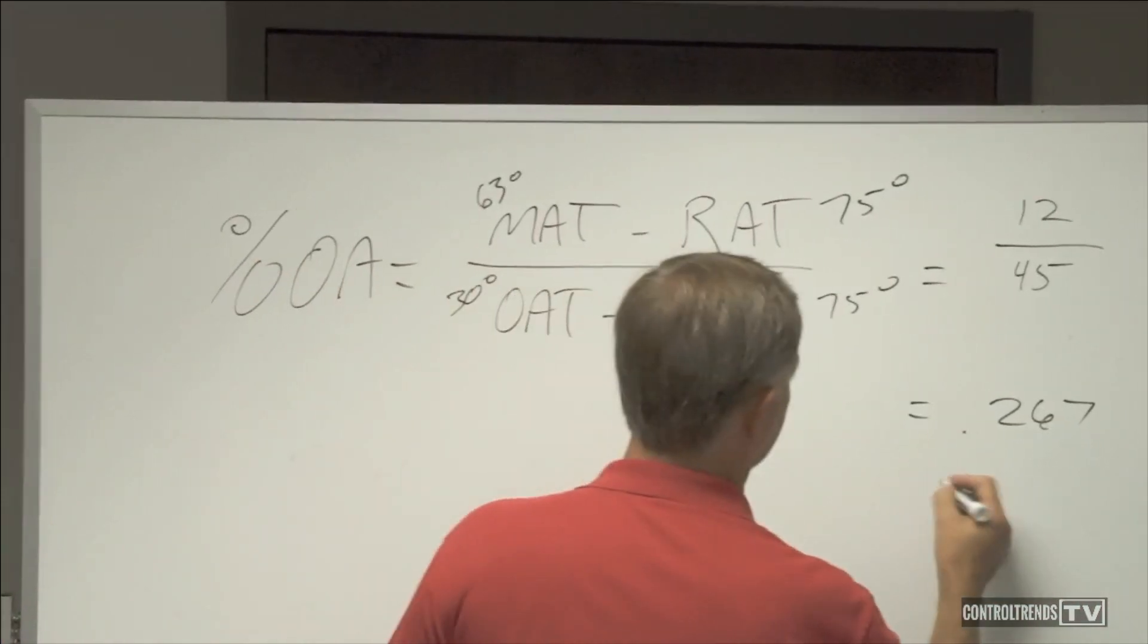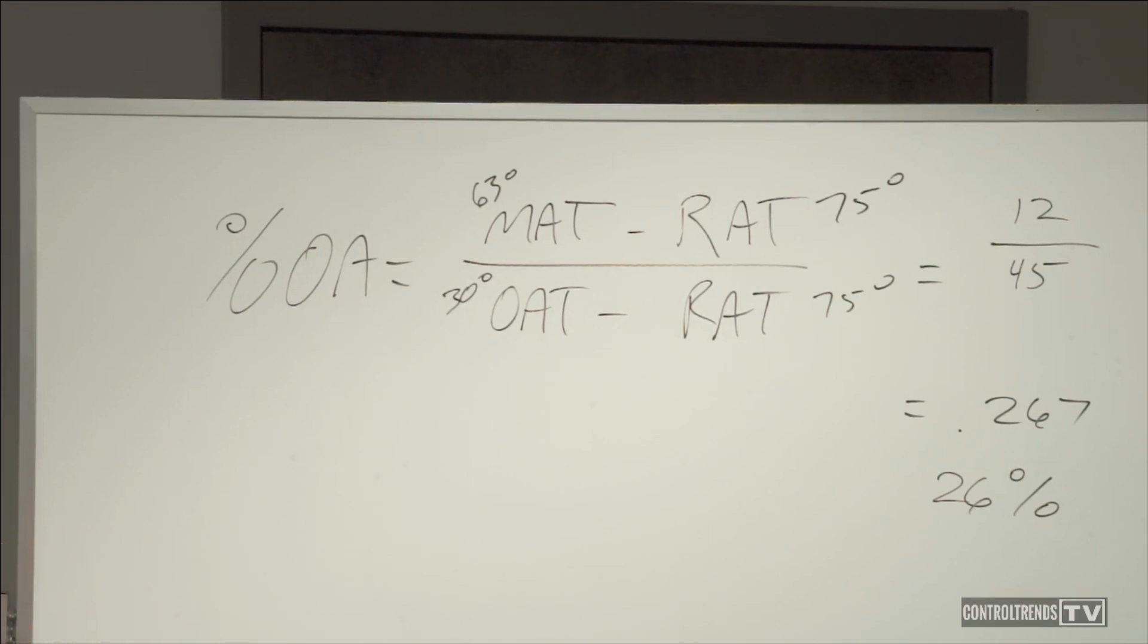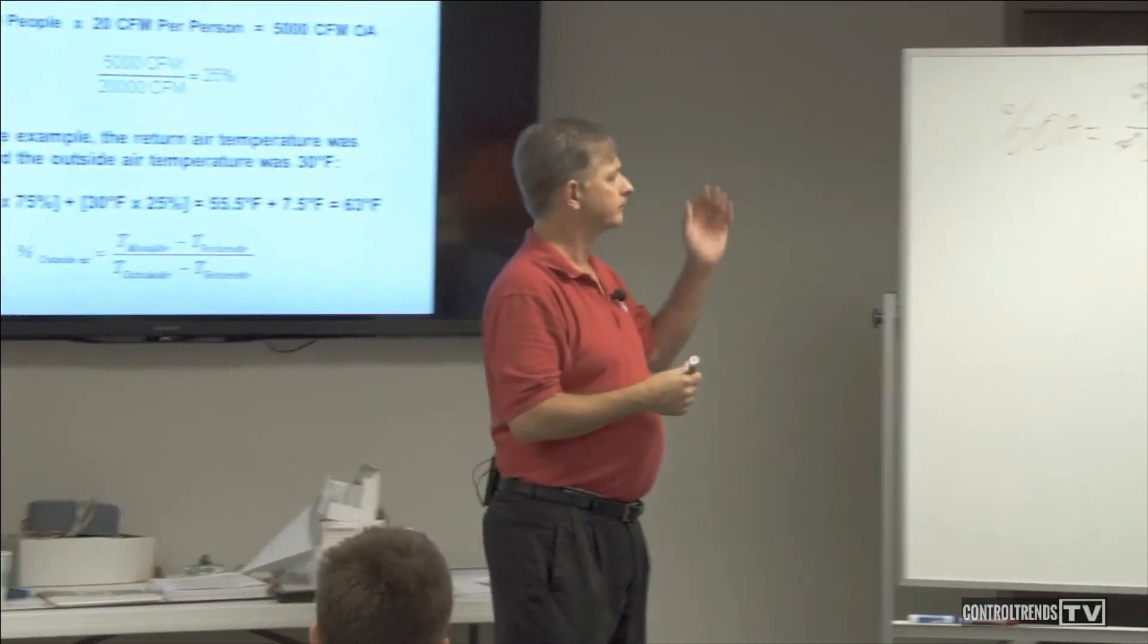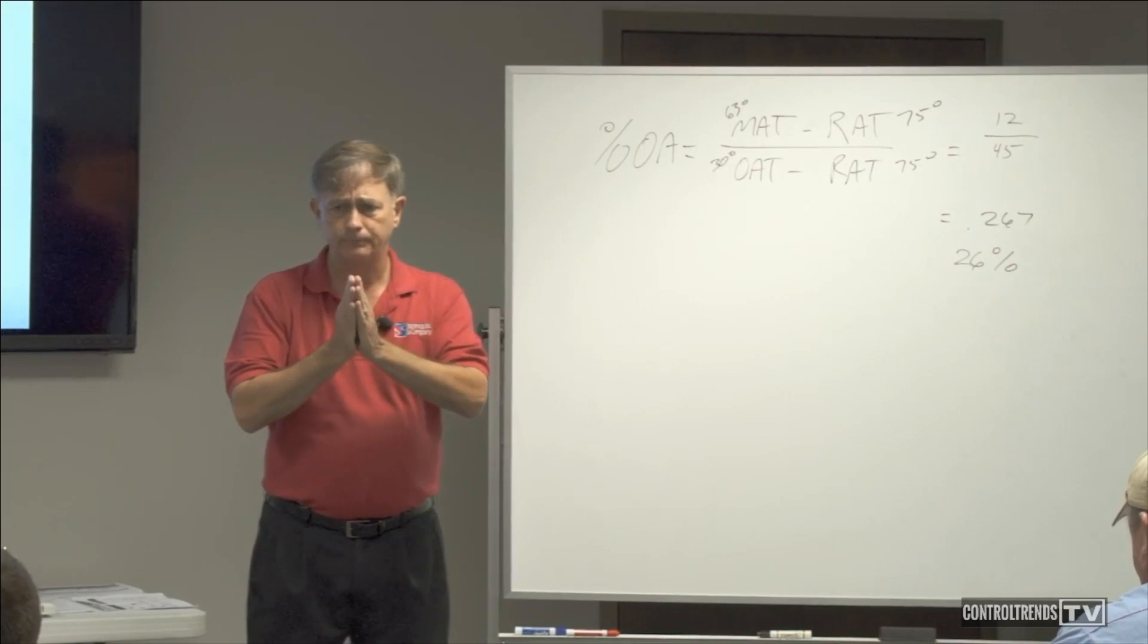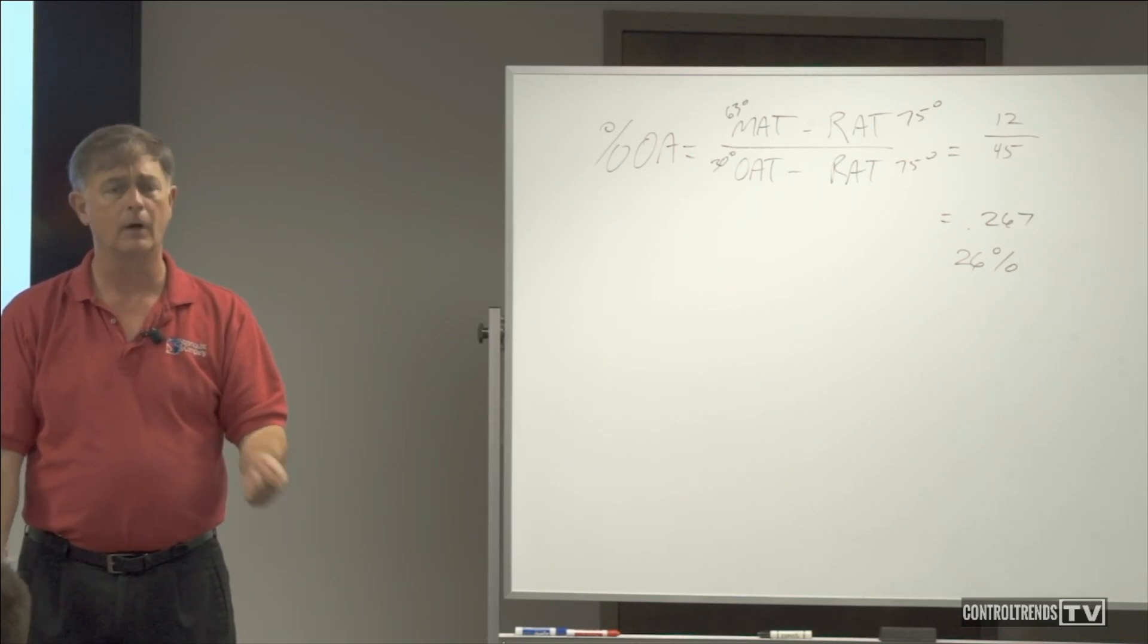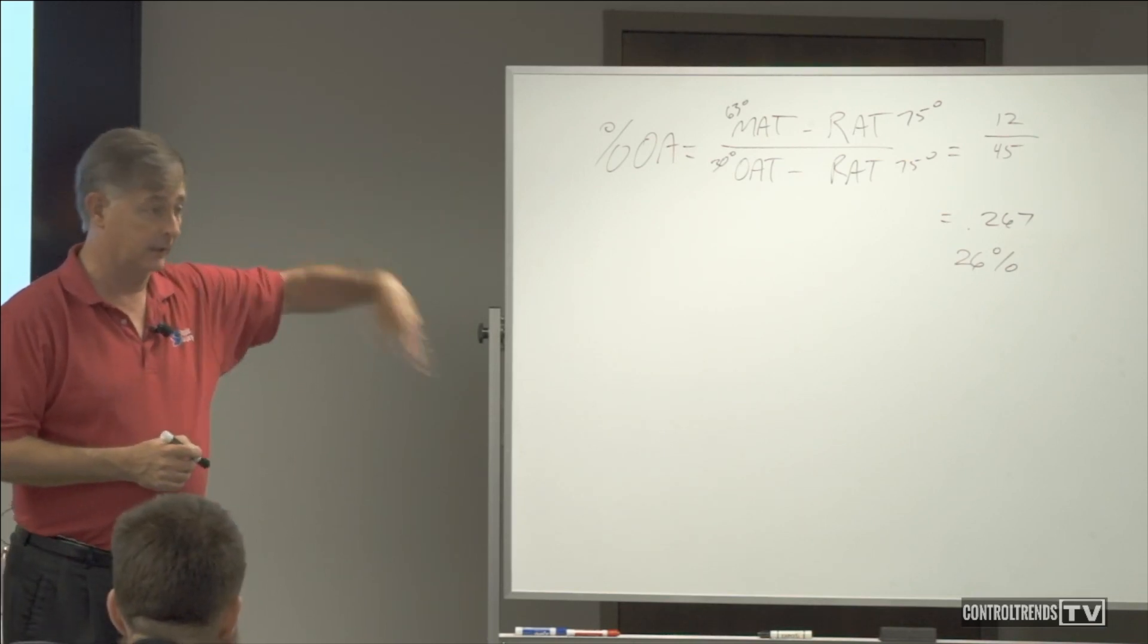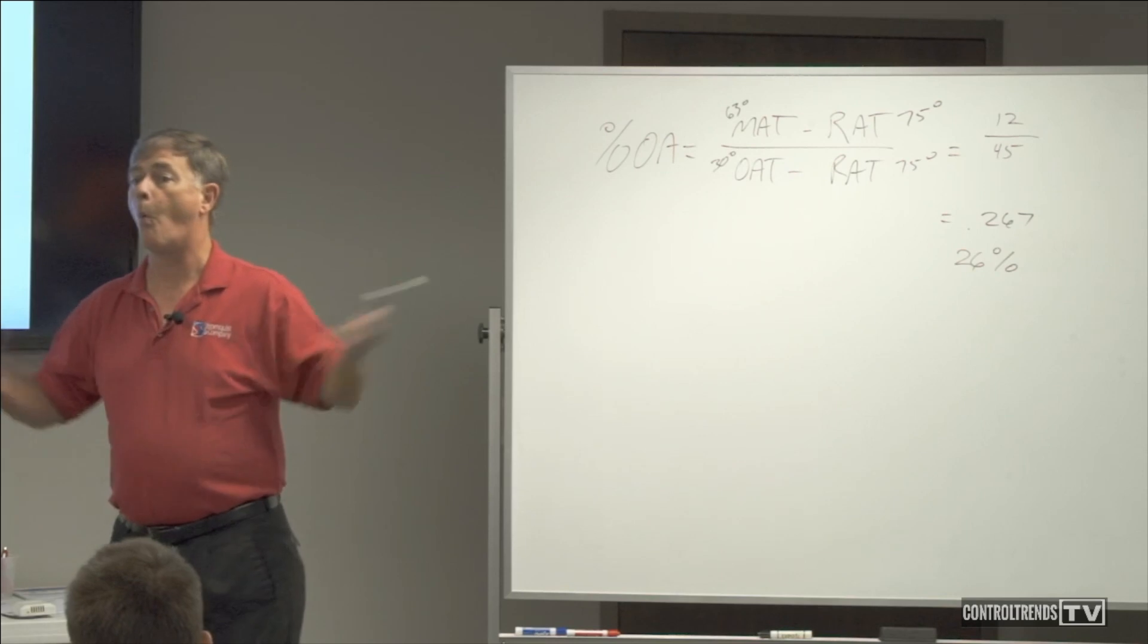So, what is that, 26 percent-ish? I don't worry about the decimal points because when you take your thermometer and stick it in there, are you leaving it in there long enough? You might be off by a half degree. So what do you think about that? Is that easy? Now, that will tell you just through temperature, taking some temperatures, working some very easy math, what your percent outside air is for that given air handler. Easy enough. Why not do it?